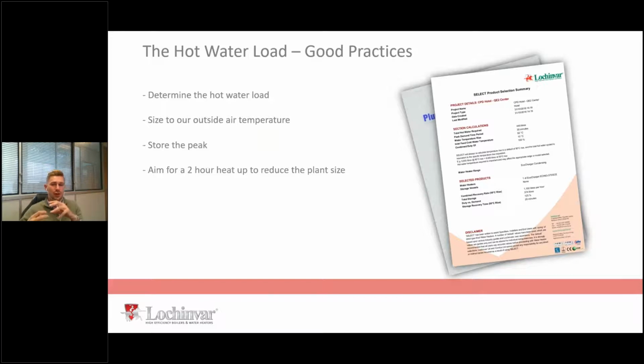Because when you look at the quality of insulation that's on storage vessels now, you'd be hard pressed to find one with less than 100 mil on it. And even then, the standing losses in megajoules a month or whatever are so minimal that actually it makes sense to have the heat pump run effectively and efficiently and reduce the number of those large current draws getting it going in cycles. The other thing that does as well, of course, is the fewer times you start it, the longer it lives. So your 2-hour heat up time plant might have a 15 to 20 year lifespan on it. Your 1-hour heat up time plant is going to have operated twice as many times in the same period, right? So in theory, it's done as much work in 10 years rather than 20. So just worth bearing that in mind in your designs for hot water.